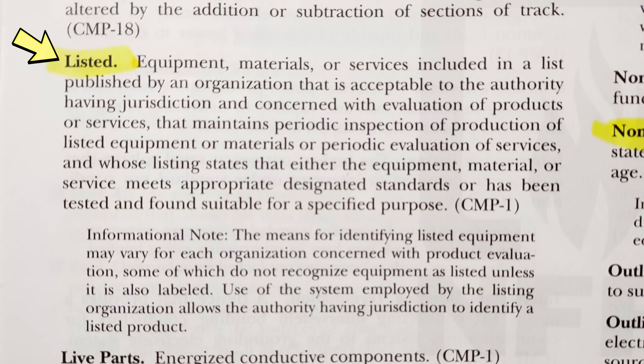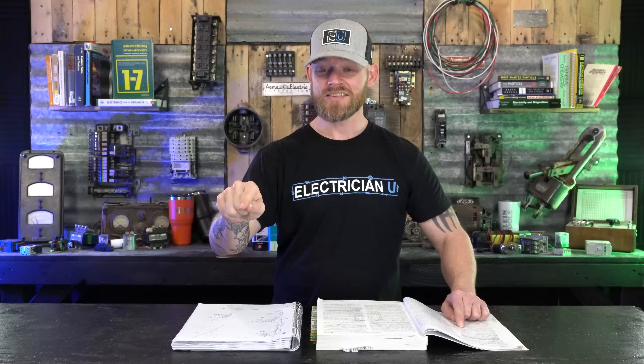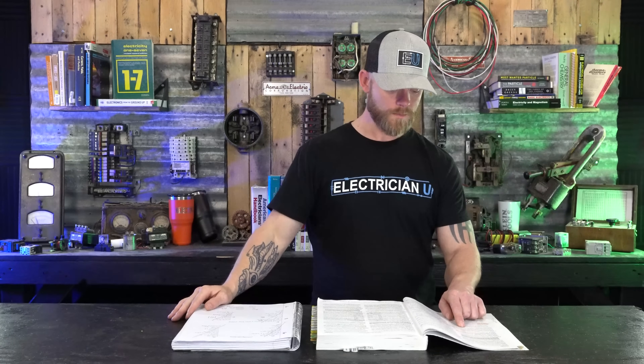Listed means equipment, materials, or services included in a list published by an organization acceptable to the AHJ, concerned with evaluation of products and services, that maintains periodic inspections of production, and whose listing states that the equipment meets appropriate designated standards or has been tested and found suitable for a specific purpose. UL, for example, evaluates things and gives a thumbs up with a UL stamp on the label. There have been cases — like the Federal Pacific situation — where they got their UL rating taken away but kept printing UL on stickers for years, even though they weren't listed, which led to lawsuits and the company closing. Not everything has to be listed, but certain things code does require to be listed.